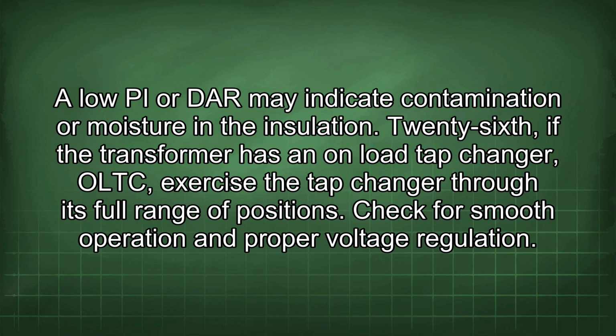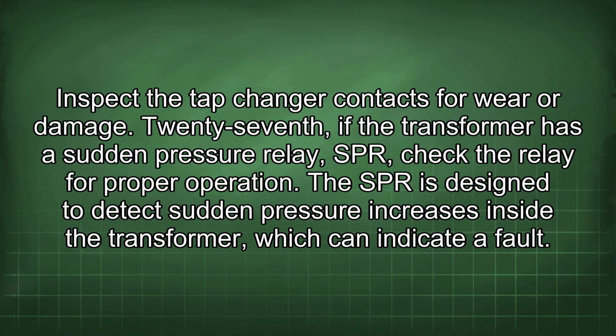26th, if the transformer has an on-load tap changer, exercise the tap changer through its full range of positions. Check for smooth operation and proper voltage regulation. Inspect the tap changer contacts for wear or damage. 27th, if the transformer has a sudden pressure relay, SPR, check the relay for proper operation. The SPR is designed to detect sudden pressure increases inside the transformer, which can indicate a fault.